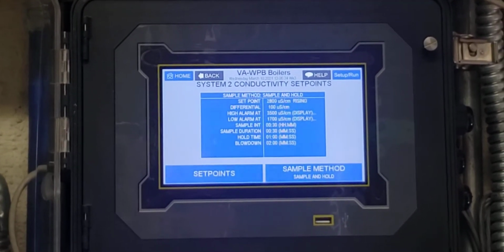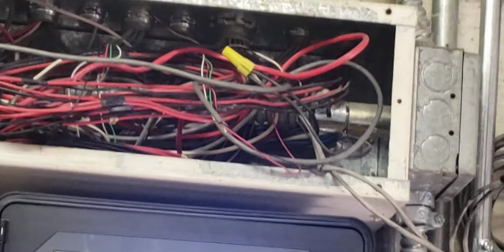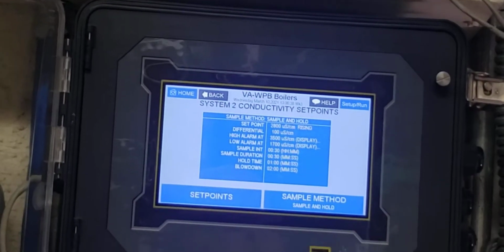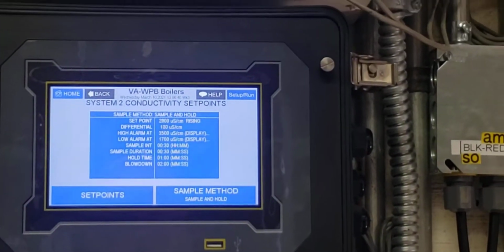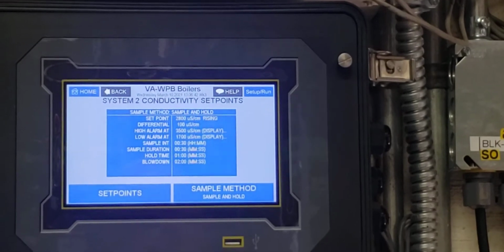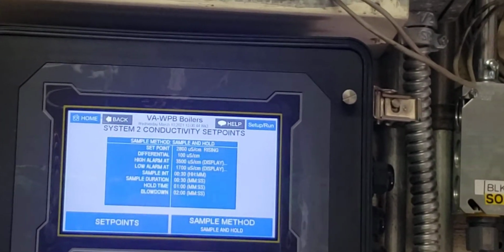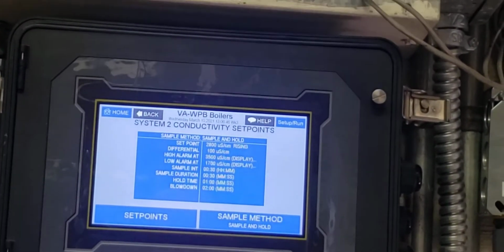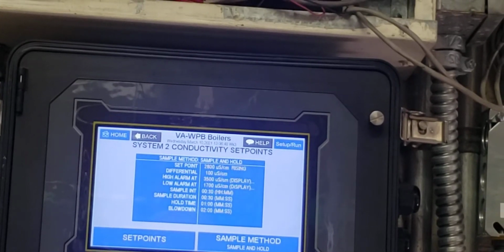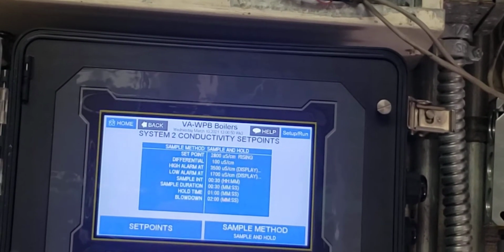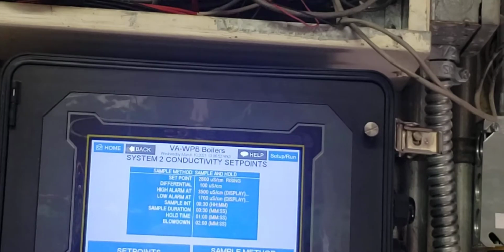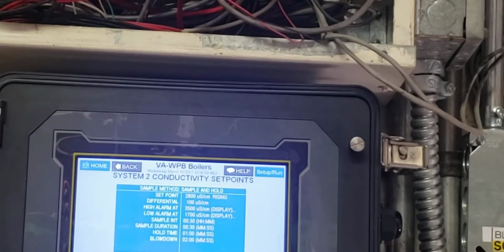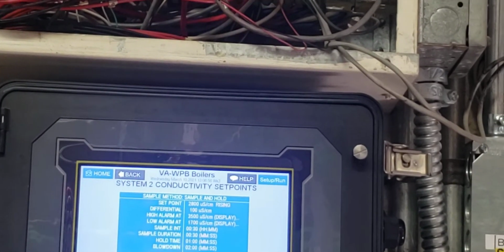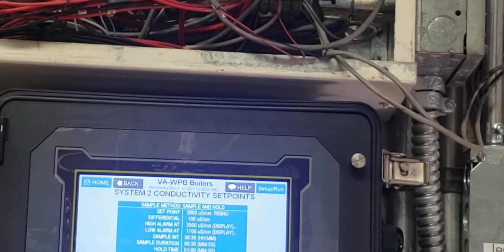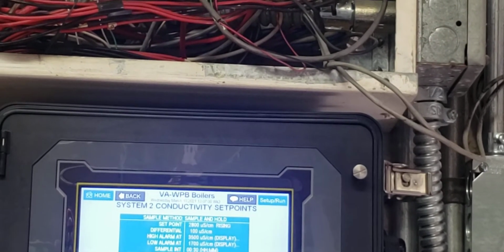30-minute hold for blowdown? No, that's a sample. That's number 1, every 30 minutes. Okay, so instead of 4 times an hour, you're doing twice an hour. Well, if you go to number 2, that's every 30 minutes. It blows down for 30 seconds, and then it holds for a minute, and then if it's high, it'll blow down for another 2 minutes. Yeah, I actually like this.